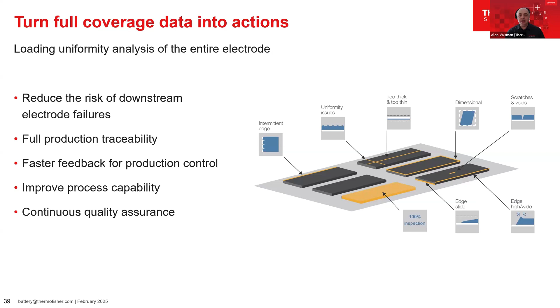Mass profilometry, on the other hand, captures a complete side-to-side loading profile nearly instantaneously, every millisecond. Operating continuously, it produces a record of the entire electrode row and makes the information and the results available in real time to help make process decisions and monitor quality. Mapping the active material loading on the entire electrode enables one to get a better understanding of the coating process performance. Edge features are analyzed in greater detail, and it becomes possible to identify spot defects like streaks, divots, and high and low loading regions.